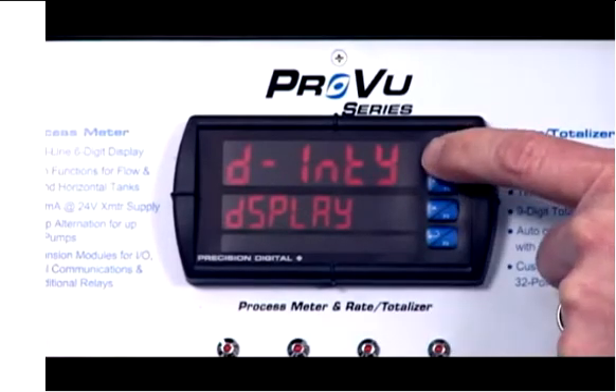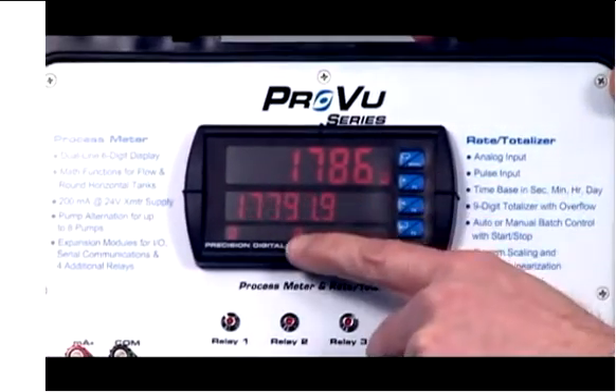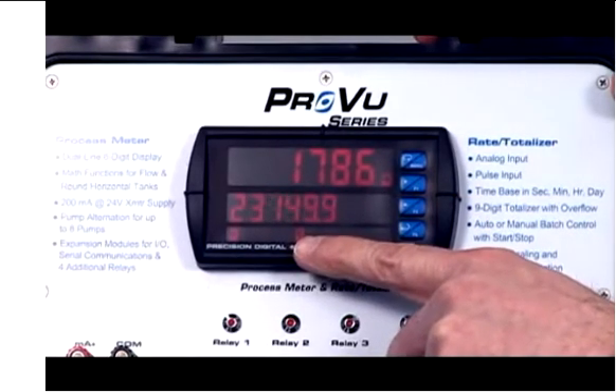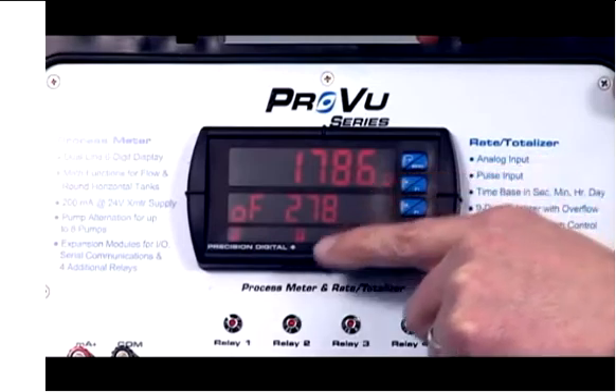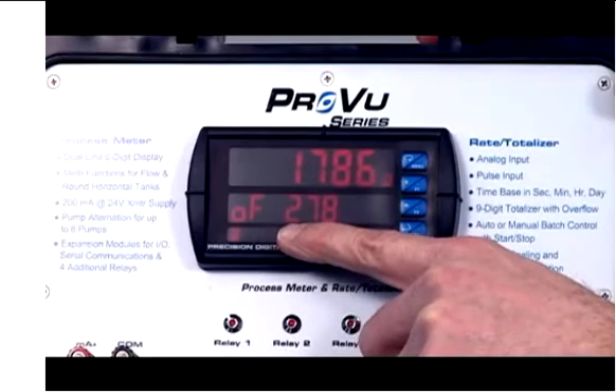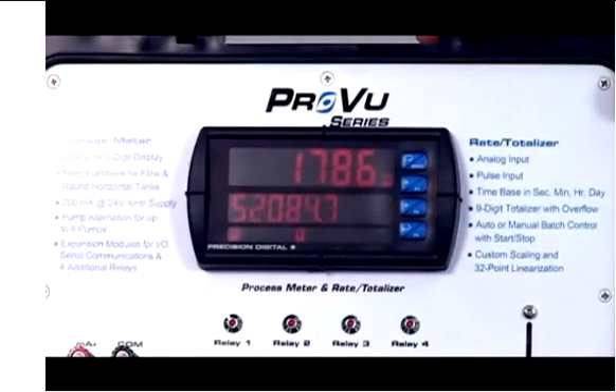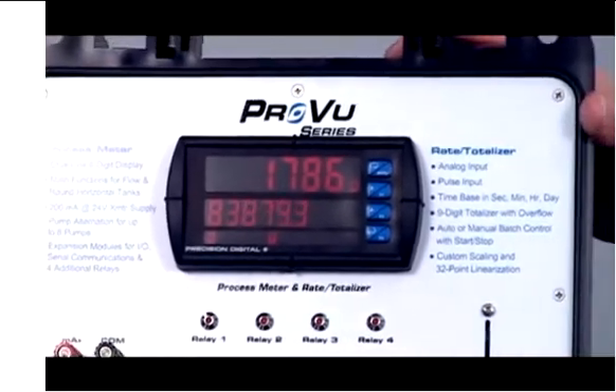We'll skip over the display intensity and go right back to the main display. Now you'll notice that right now we are totalizing — we're at almost 200,000 gallons and up above we're displaying rate. Down below we're actually in the overflow mode, indicating we are displaying 278,457,000 gallons. So the ProVu can actually display up to nine digits for total. We can also program the ProVu to be set up for non-resettable total, so there really are quite a lot of features specifically designed for flow rate and total.